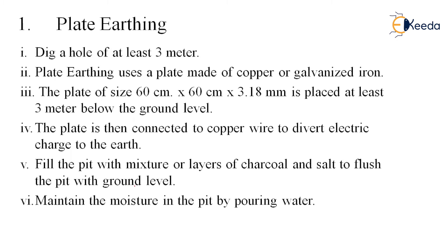Let's see what is plate earthing. First, dig a hole of at least 3 meters depth. Plate earthing uses a plate made of copper or galvanized iron. A plate of size 60 cm × 60 cm × 3.18 mm is placed at least 3 meters below the ground level. The plate is then connected to a copper wire to divert the electric current to the earth. Fill the pit with alternate layers of charcoal and salt to flush the pit with the ground level.